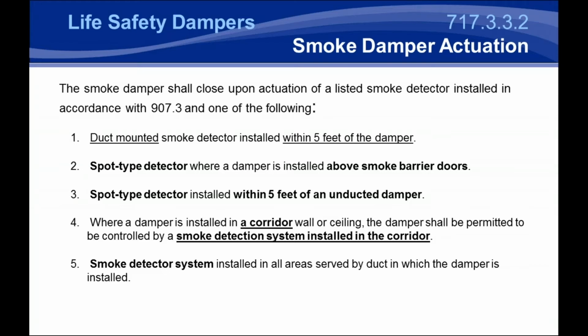And because a lot of times these dampers are installed tight to a wall or a ceiling, there isn't a whole lot of flexibility once you have protrusions on either side of the damper. Because of that, we typically recommend shipping smoke detectors loose for field install. Now, of course, if you've already got smoke detectors because you are by a corridor, you can use that smoke detection system to operate and close the damper as well. So you may not need an additional smoke detector from a damper manufacturer.